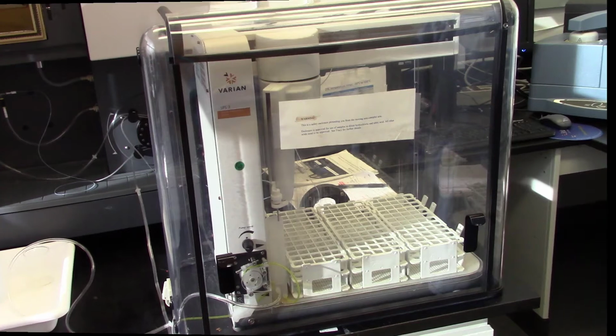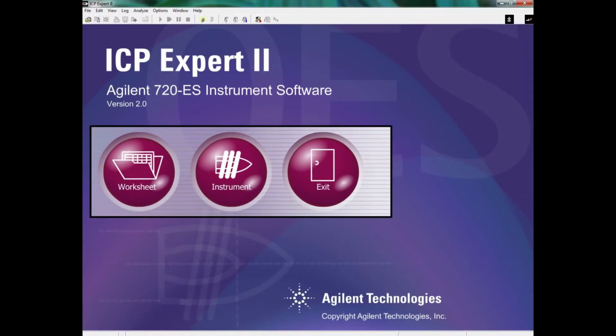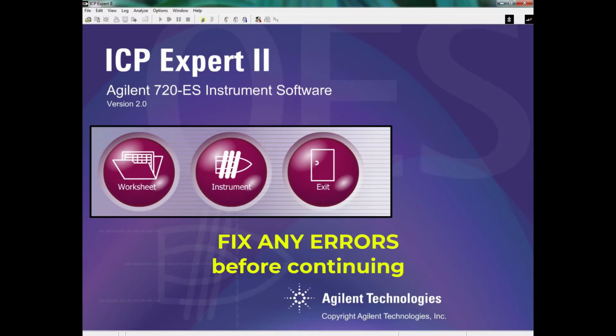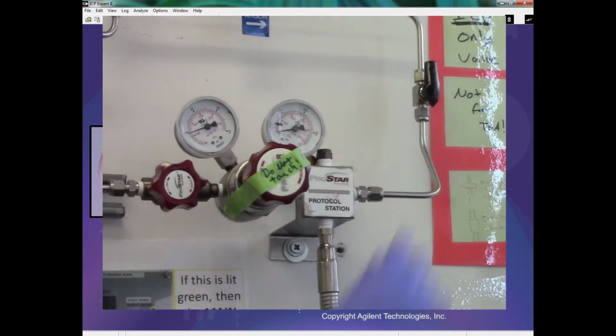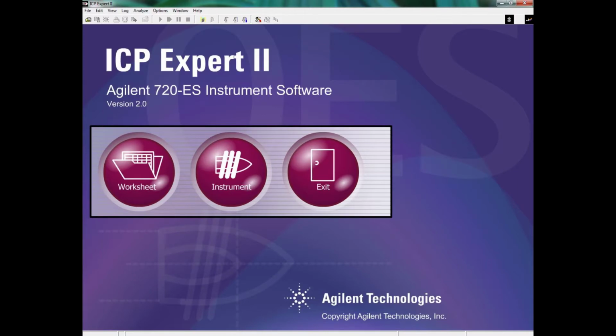Once everything is on and ready, open the software by pressing the ICP Expert 2 icon on the desktop. If any errors pop up, immediately remedy the problem before continuing. In most cases, this simply means remembering to open the gas valve on the wall. Contact the staff member responsible if the fix is not immediately obvious. If your gas flow and chiller are okay, you will have 20 minutes to wait until the torch can be started. This is fine though, because you'll need time to set up the program.